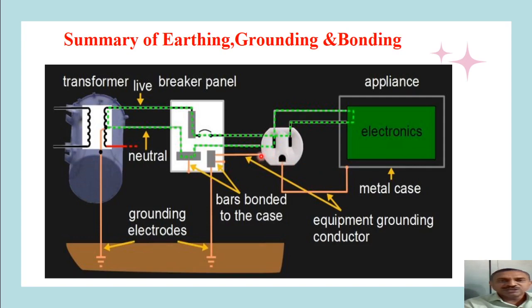Again the distribution box and panel boards will be held at same potential of breaker panel body. So all these three will be bonded together and they are connected again to the earth through the grounding electrodes. So here we can observe in this figure that there is a neutral grounding, what we called as normally grounding, and earthing, body of various equipments, and at the same time bonding of the equipment's body so that they will be always held at same potential. With this I am sure that you understood the meaning of earthing, grounding and bonding and their significance in electrical system.